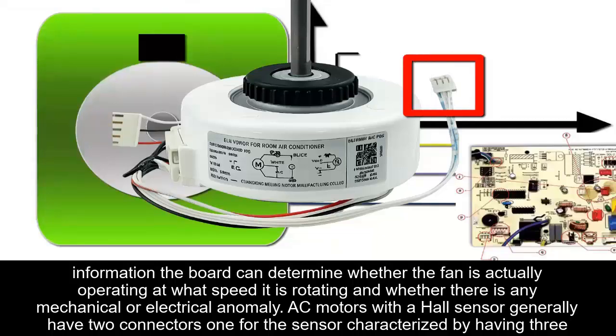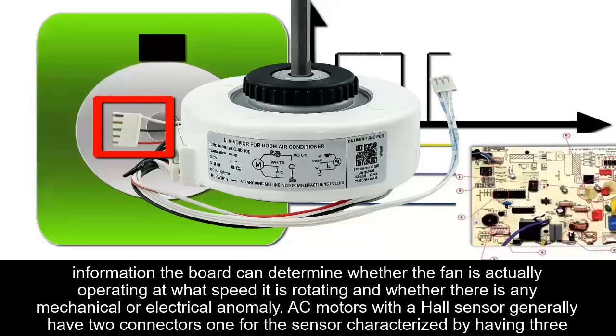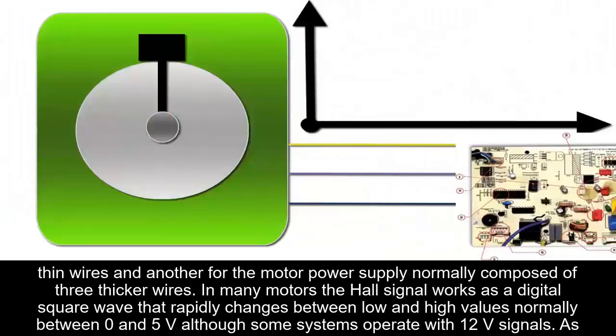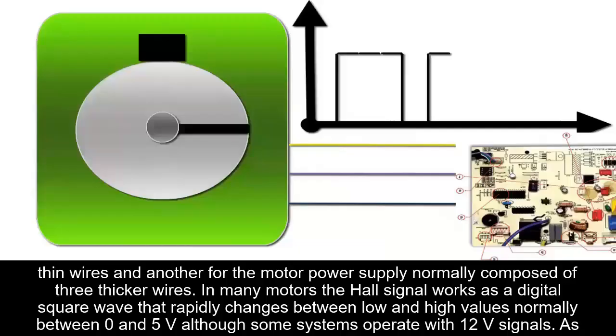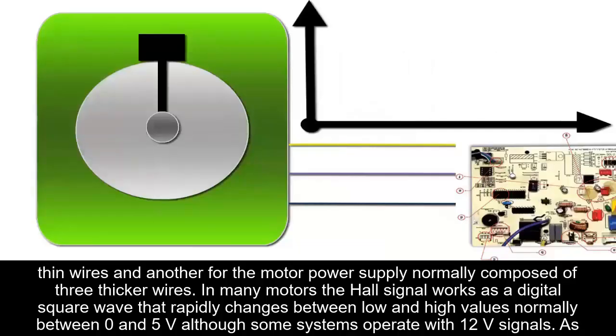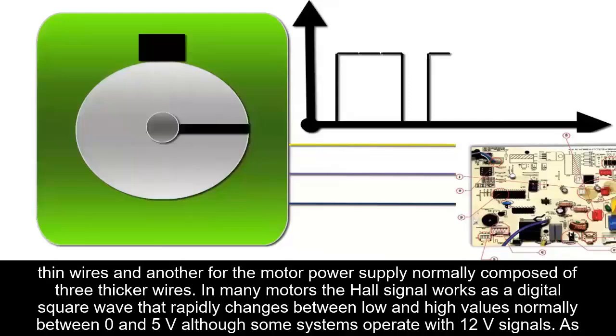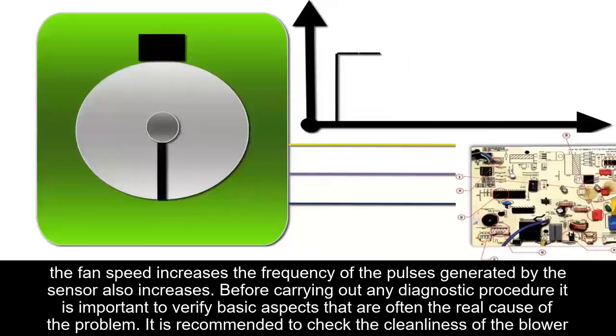AC motors with a Hall sensor generally have two connectors, one for the sensor, characterized by having 3 thin wires, and another for the motor power supply, normally composed of 3 thicker wires. In many motors, the Hall signal works as a digital square wave that rapidly changes between low and high values, normally between 0 and 5 volts, although some systems operate with 12-volt signals. As the fan speed increases, the frequency of the pulses generated by the sensor also increases.